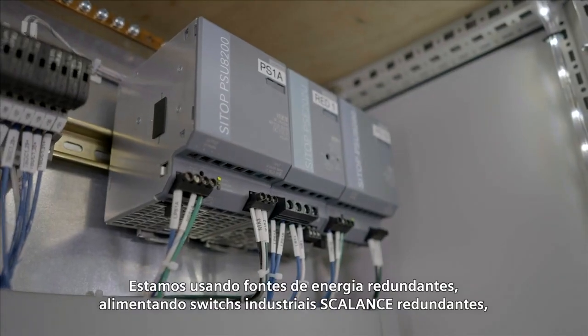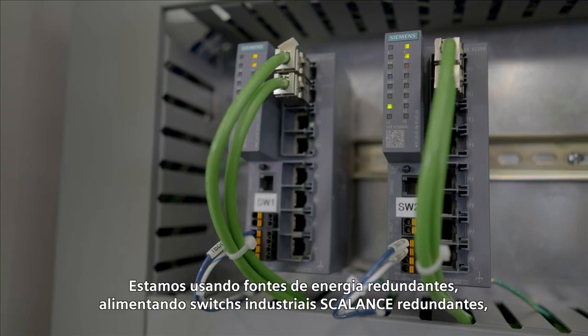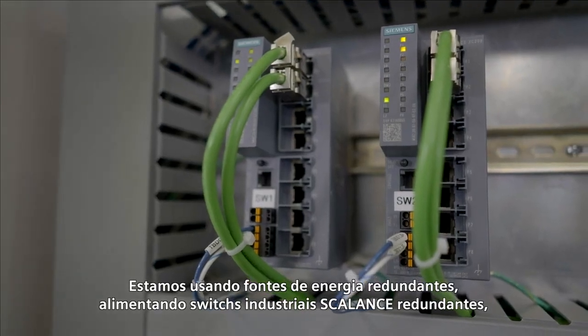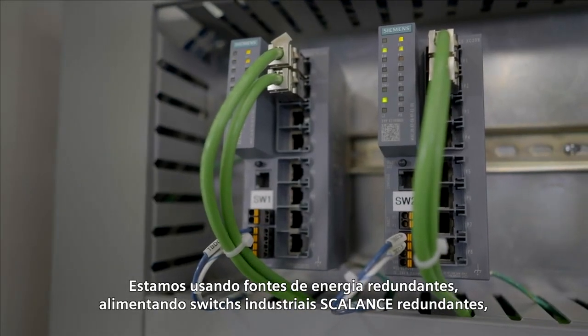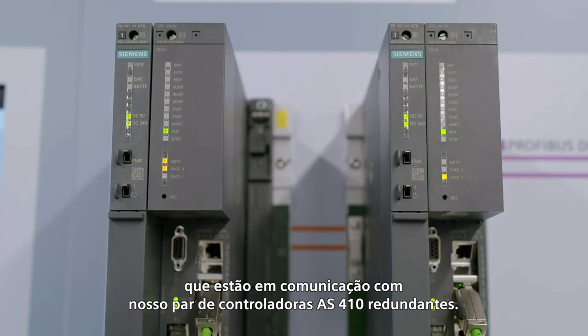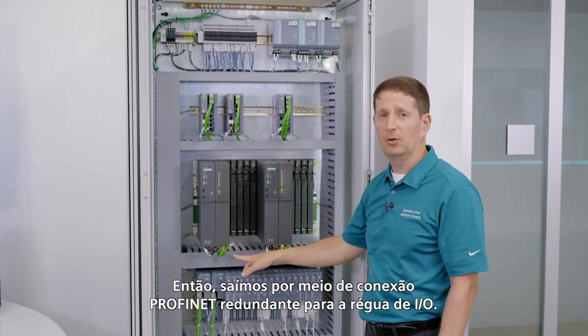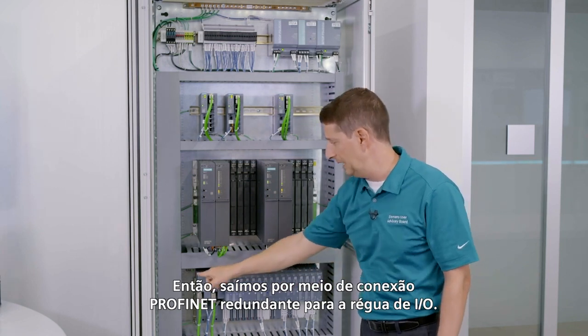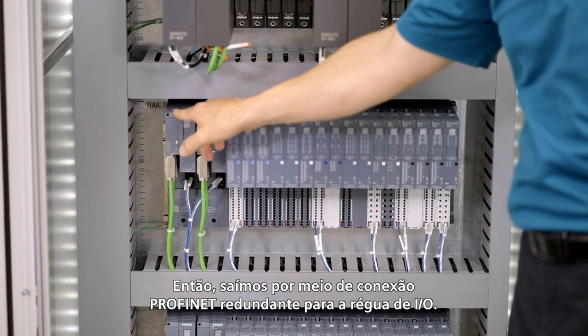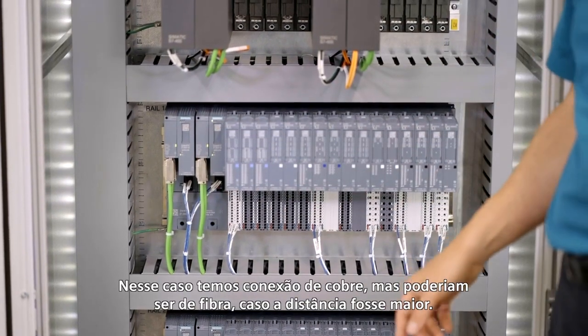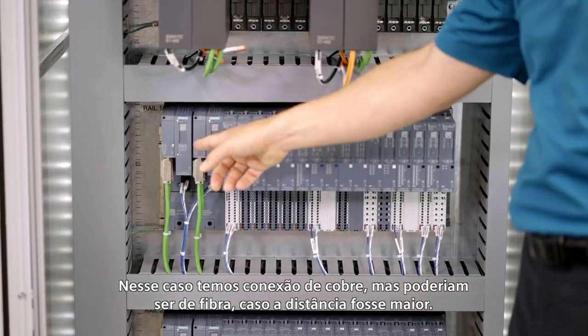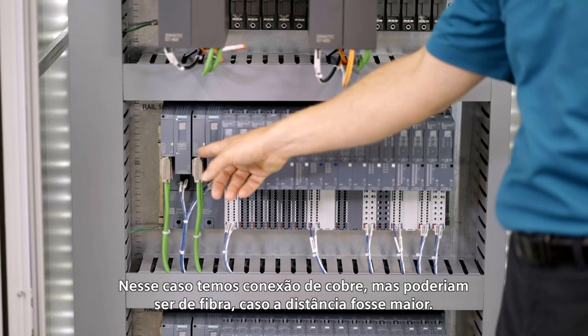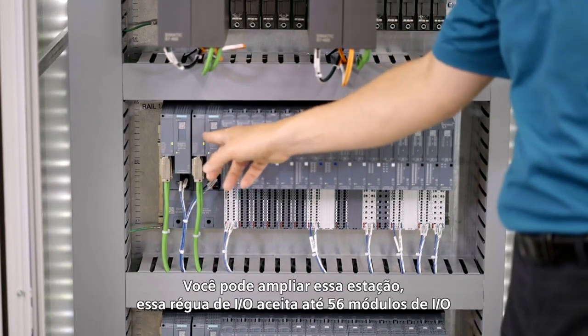We're using redundant power supplies, which are going to redundant industrial SCALANCE switches, which then communicate to our redundant AS410 controller pair. From there, we're going out via redundant Profinet to the I/O rail. In this case, we have copper connections, but these also could be fiber if the distance was further. You can extend this here.